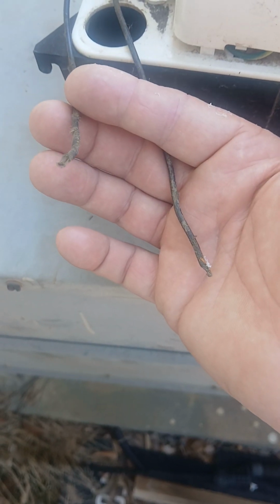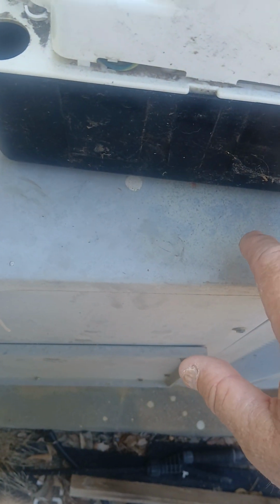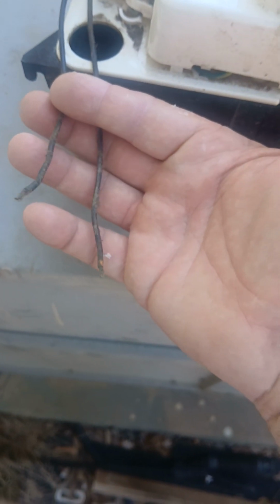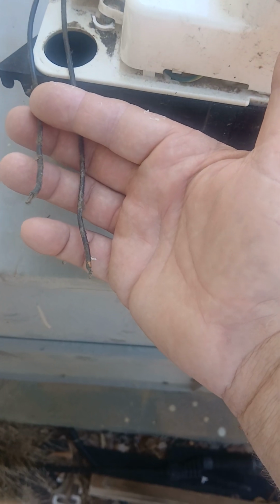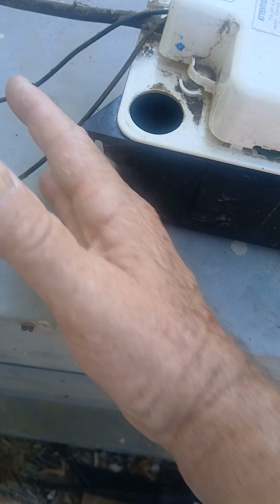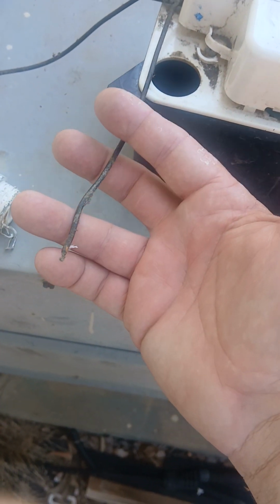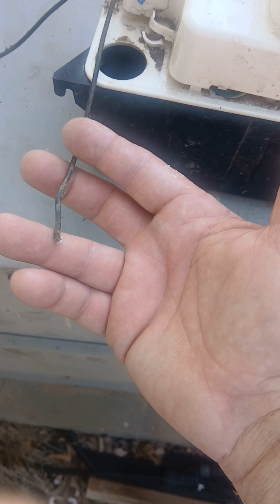But let's just hypothetically say we wired it in, split the red one side, grab the other side with the red. So what would this do? If the water comes up long enough, it would act like a relay, and then it would shut this pump off. So, let me rephrase that. That may be incorrect. It may shut the system off, because the electricity has to make a full circle. It needs to go all the way around 360 degrees. So if we short this out, or we open the circuit or the relay, I don't know what nomenclature would be good, but if we open that, then it would shut the entire system down.